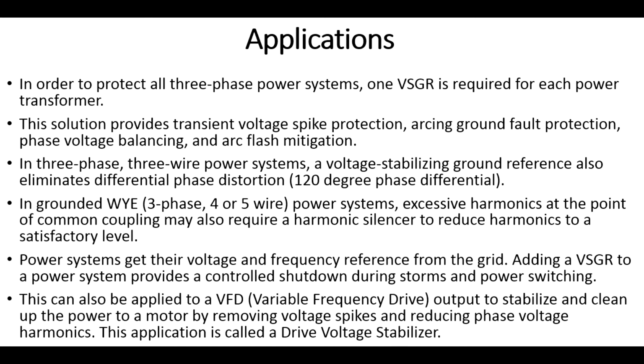If you can reduce the harmonics, typically by 85%, if you can eliminate the voltage spikes above the peak voltage level, then this standing wave or reflected wave is no longer a problem, and you can run as much as 1,000 feet of motor power cable between a drive and motor, allowing you to install the drive in a more convenient location rather than having to put it close to the motor.